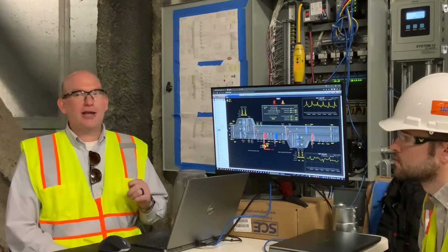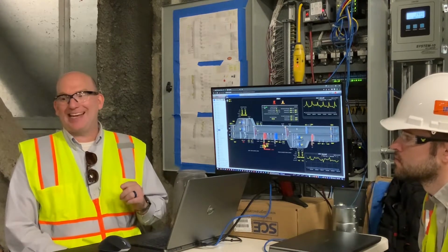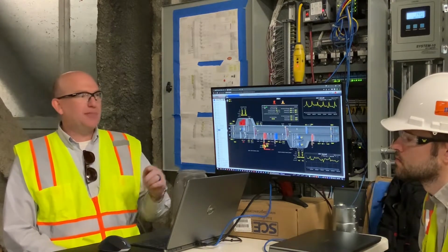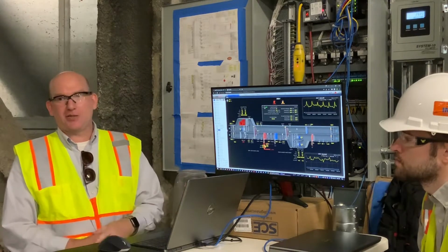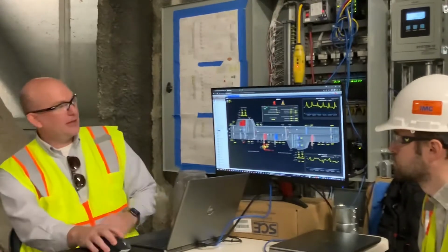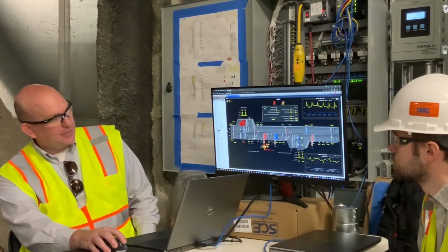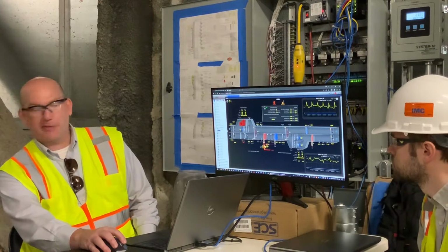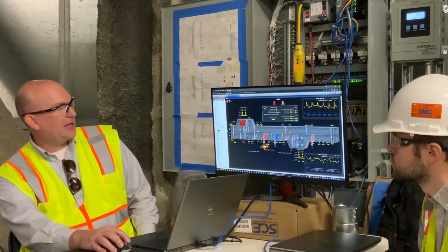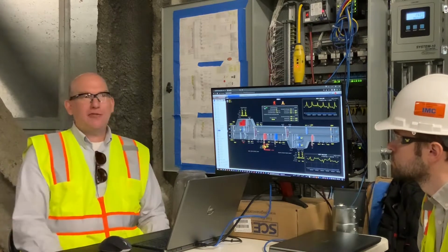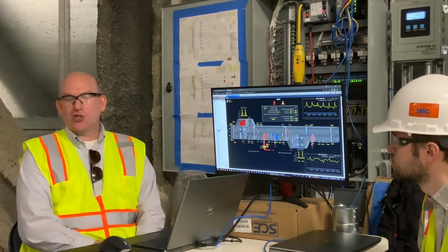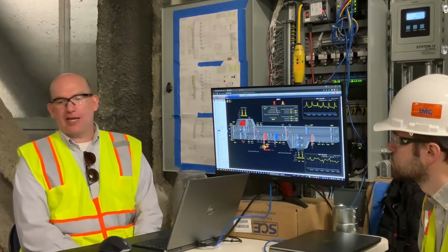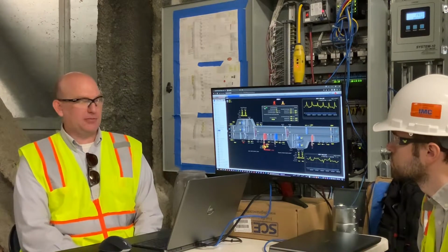The fan will start and run to a minimum speed set in the VFD. That minimum speed is usually 1/3 of its maximum. And the dampers here in the discharge of the supply and the dampers in the exhaust are all rated for 8 inches of pressure. So running a fan at minimum against those dampers should not cause you a problem, right?